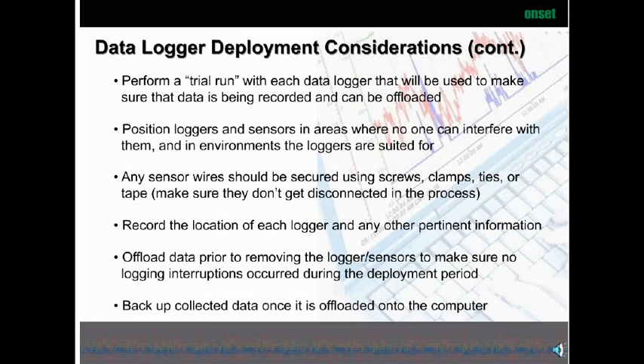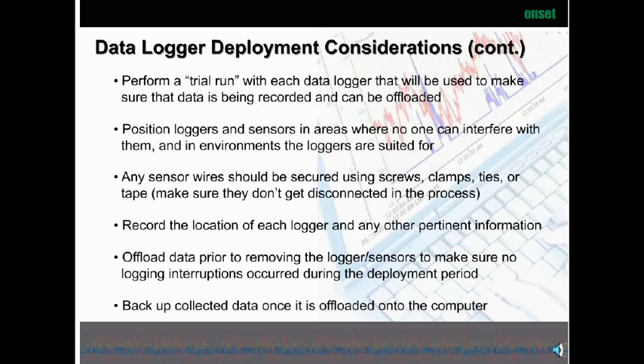Some other considerations. One thing I highly recommend is that you do a trial run. Prior to leaving the logger at a location, run it — make sure it's doing its job. Set it up for a five-minute cycle or even longer if you want. Make sure you run it to confirm all the sensors are coming in and everything is functioning properly. It's an extra step, but it can save you a lot of pain and suffering if you come back and don't have the information in the logger configured properly.